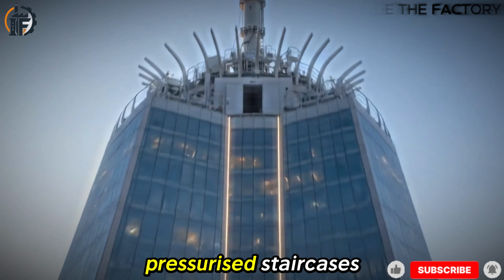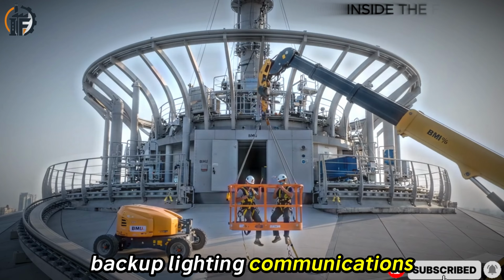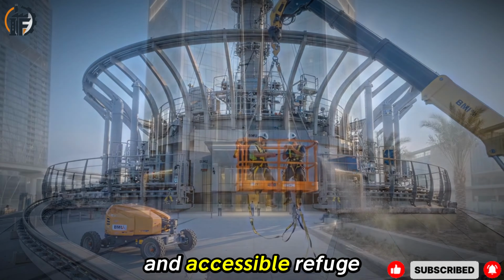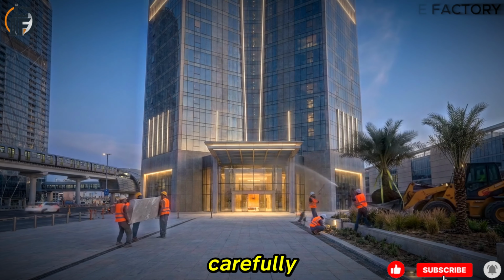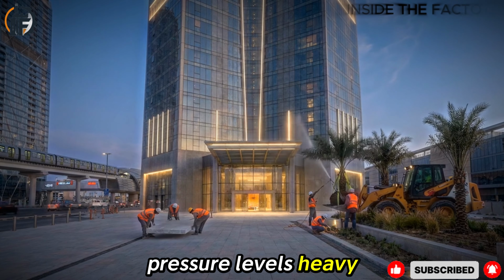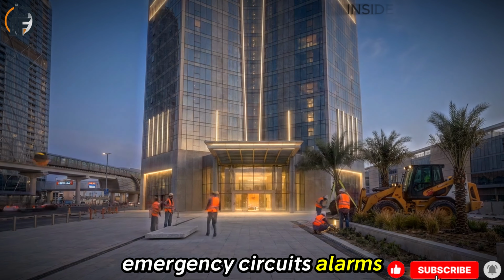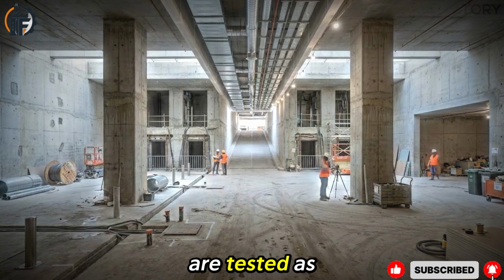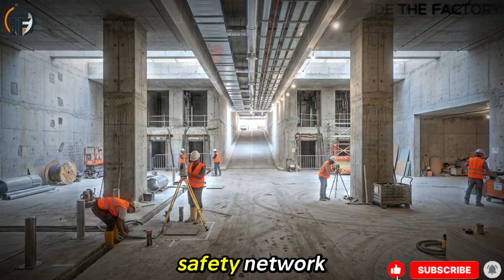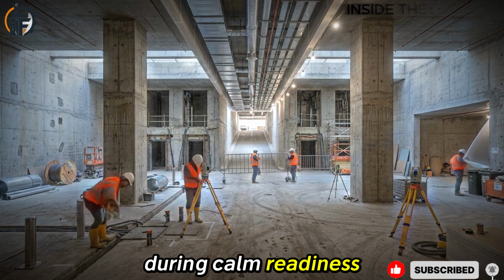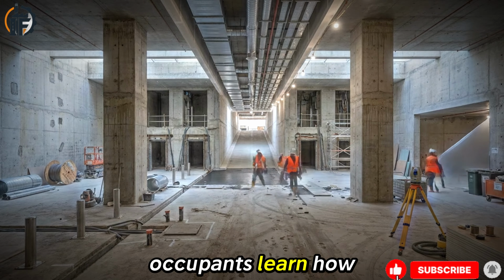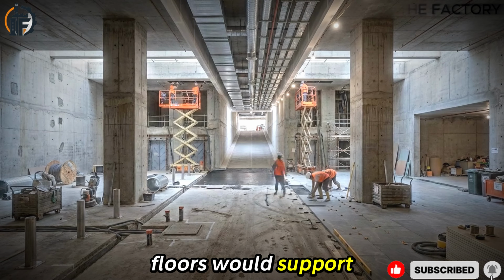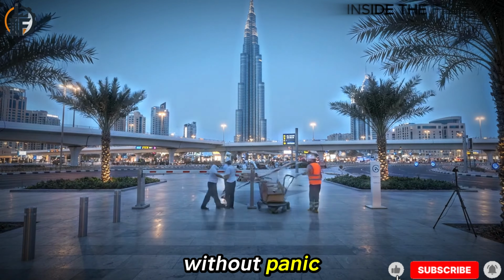At intervals higher in the building, refuge floors provide protected spaces during a high-rise emergency. Fire-rated walls, pressurized staircases, backup lighting, communications, medical support points, and accessible refuge areas are installed carefully. Pressure levels, heavy doors, emergency circuits, alarms, and ventilation systems are tested as one coordinated life safety network. During calm readiness drills, occupants learn how these protected floors would support an evacuation without panic.